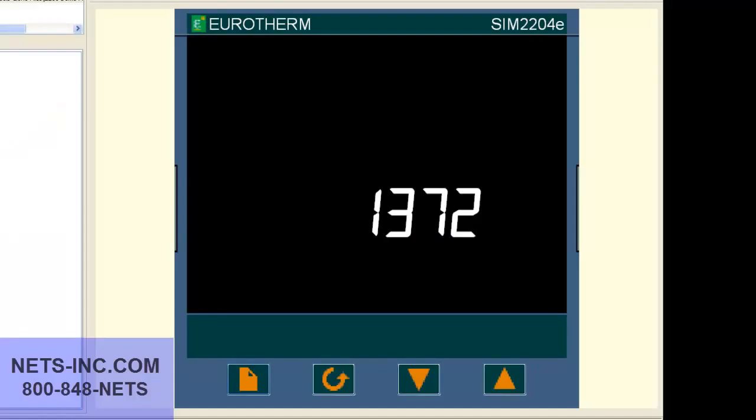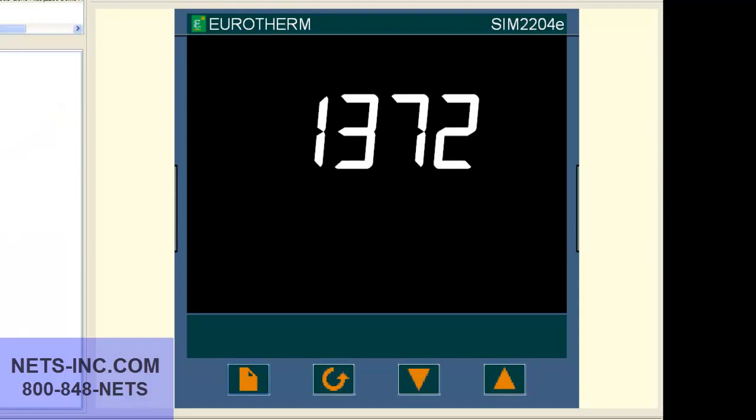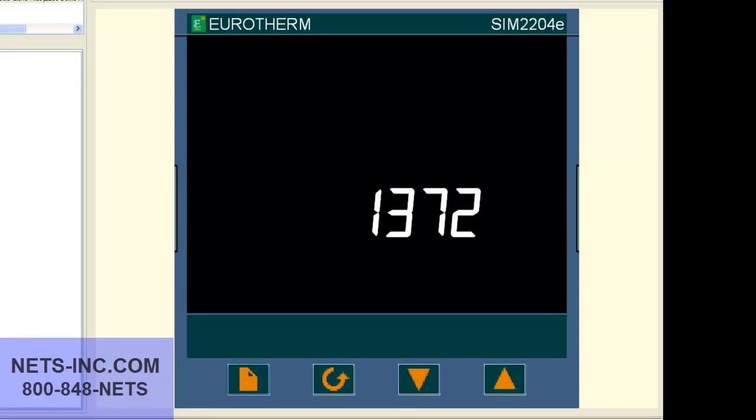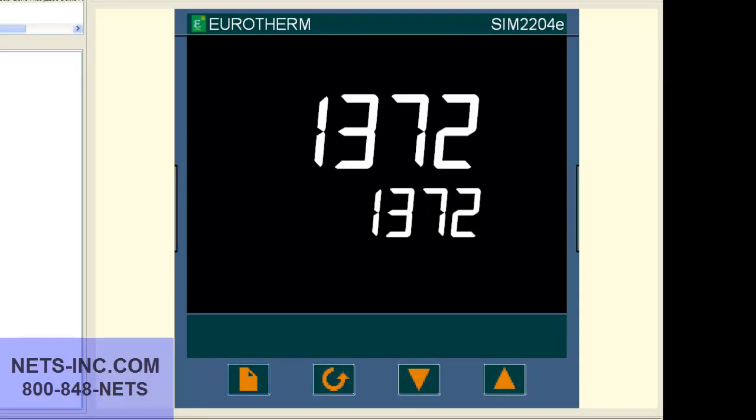This video tutorial will show you how to change the control action from reverse acting control, typically a heating application, to a direct acting control, typically a refrigeration cooling application, on a Eurotherm 2200 series controller.